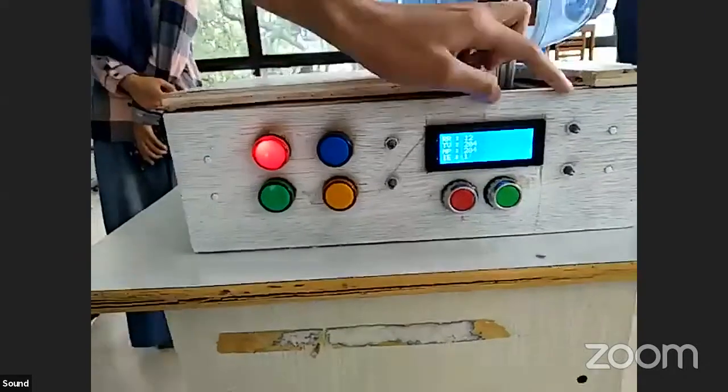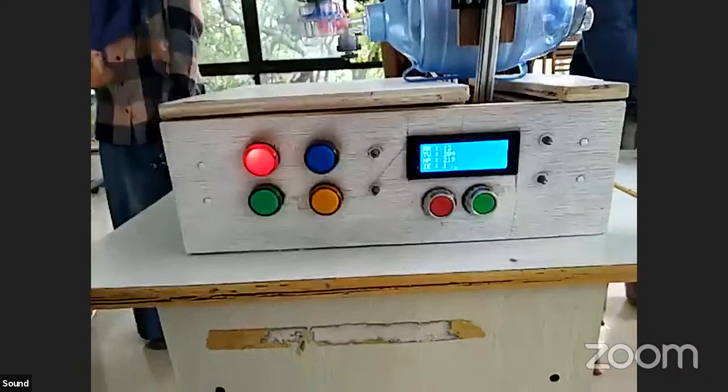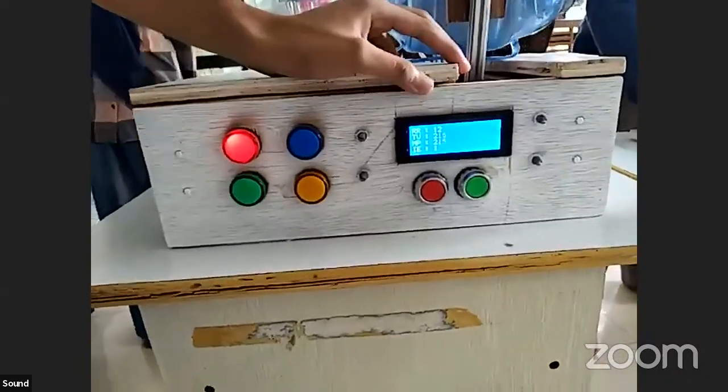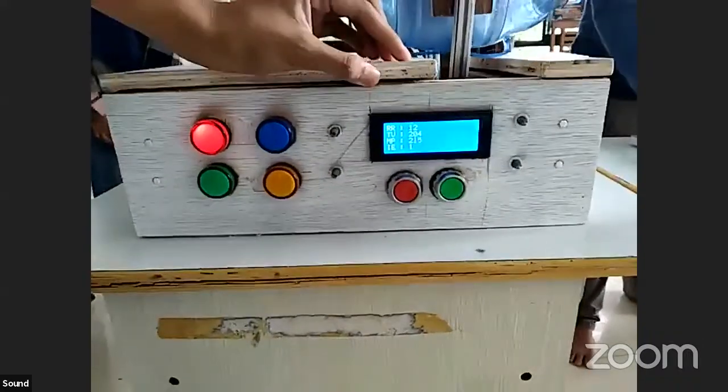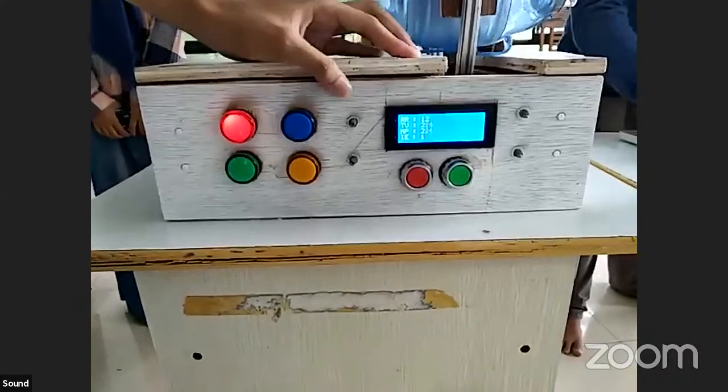So to use it, you have to change the parameters using these four knobs. There are four knobs. This is the respiration rate knob. This is the tidal volume knob, maximum pressure knob, and inhale exhale ratio knob. You have to change it based on the patient condition. For example, a baby and a mature human are different. They have different tidal volumes of their lungs.